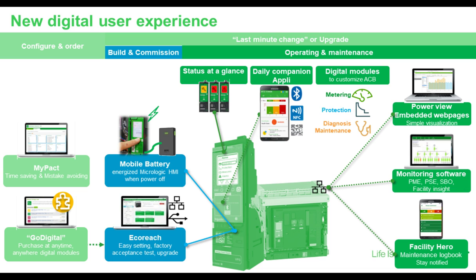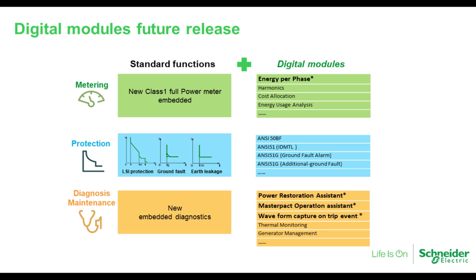We can also now, with communications, bring that data out of the trip units up to different softwares so that we can monitor, and we can also look at maintenance. We can monitor what's occurring within that trip unit and what's occurring within that breaker, and looking at times when we have to do additional maintenance to the equipment. And last is basically getting all that digital information up to a higher system so that operating and maintenance can look at more predictive possibilities and predict failures before they even occur, which will reduce many of the downtime incidents that do occur.